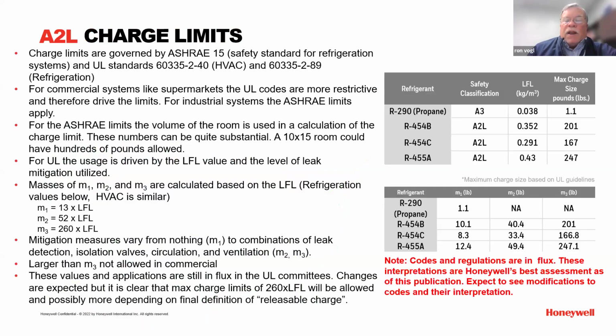I want to talk a little about the LFL, the lower flammability limit. Refrigerants have a range of flammability, and in the charts you get from some manufacturers there's a formula and probably a table. M1 basically is a class of refrigerant you can use based on room size - typically a 3-ton residential air conditioning unit will be M1 and you won't have to do anything. M2 is where you start to have a smaller space, or other flame possibilities, and it's all written out in the standards and literature. You just multiply by a different number, giving you more restrictions, or you can use a larger charge if you've got isolation valves, leak detection, ventilation, and so on.